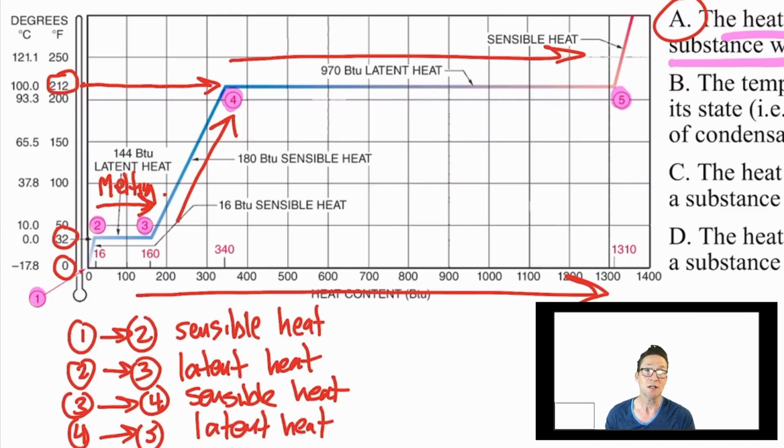Now, eventually, you'll run out of liquid to boil. All of the liquid water will turn into vapor, right? It's like a boiling pot of water. The vapor leaves the pot. There's no more liquid to boil. But that vapor can still be heated. In fact, you can superheat it. It's the definition of superheat: adding a certain amount of sensible heat energy to a gas that causes an increase in its temperature. We look for superheat at the outlet of evaporators, don't we? It's just that we're talking about refrigerant and not water.